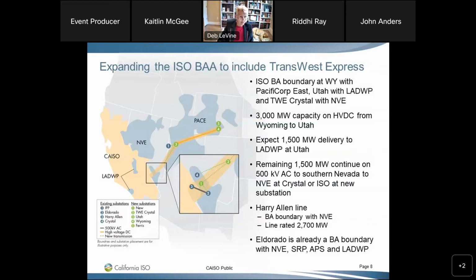The 3,000 megawatts of wind generation will be connected at the Wyoming substation. From Wyoming all the way down to Utah is a 400-plus mile high voltage DC line running from Wyoming down to Utah. In Utah it'll be converted to AC, with the opportunity to move 1,500 megawatts onto LADWP's existing infrastructure up in Utah.